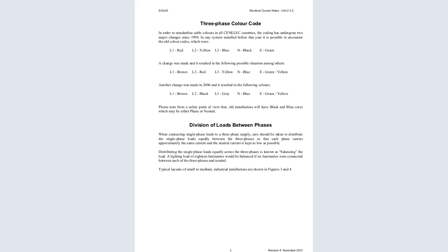Three-phase color code. Now we have the color codes here. In order to standardize cable colors, the coding has had to undergo two major changes since 1990. In any system installed before that year, it is possible to encounter the old color code, where line 1 was red, line 2 was yellow, line 3 was blue, N was neutral, and E, the earthing, was green.